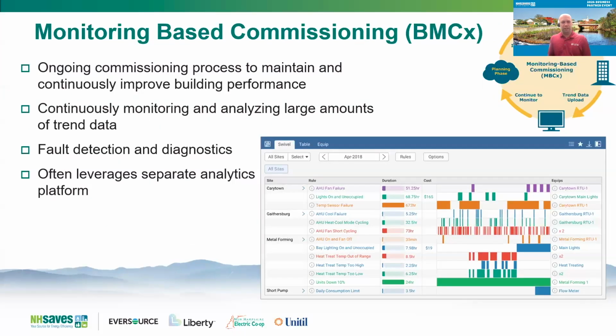We'd be remiss if we didn't mention monitoring-based commissioning quickly. Not the focus of today's discussion. The focus really is retro-commissioning, which is, I like to think, what should be done first. You want to retro-commission a control system to get it modernized, get it up to snuff, get it operating efficiently. And then once you've got a fully modernized, well-functioning control system, you can look at monitoring-based commissioning, which is ongoing, leveraging trend data to continuously monitor and identify opportunities, fault detection and diagnostics, finding issues based on data. But you really need to have a modernized, well-functioning control system.